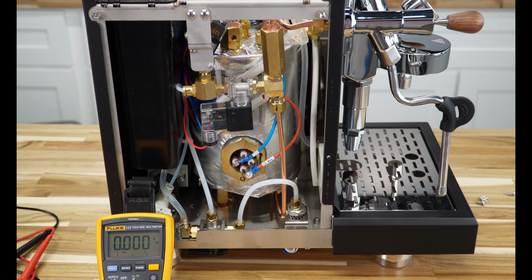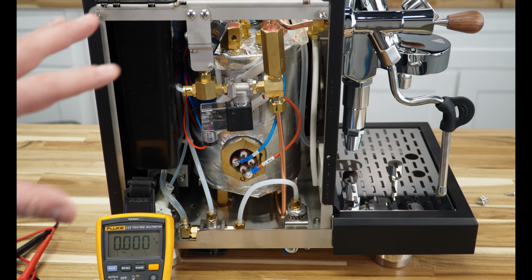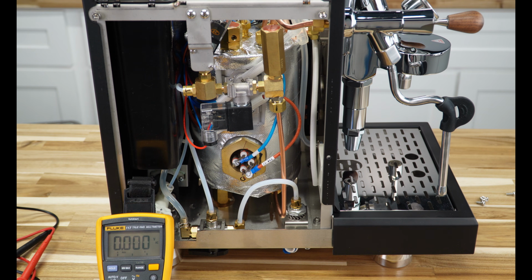So really what happens with these, they're really not the most precision piece to begin with, and they will get corrosion inside of them. Sometimes they'll get stuck in that off position. So everything else seems like it's working. Your pump turns on, but it's just not heating up. I would probably check your pressure stat, at least if it's an older machine with the pressure stat.